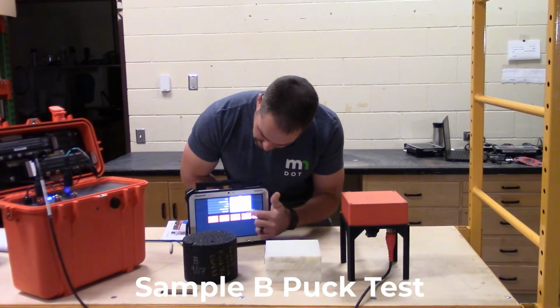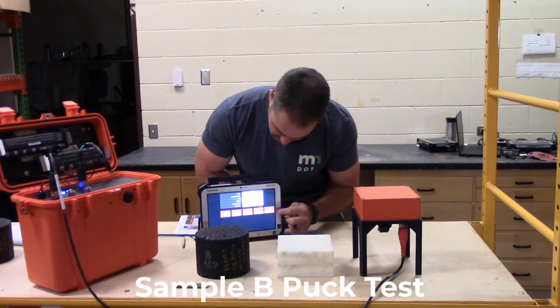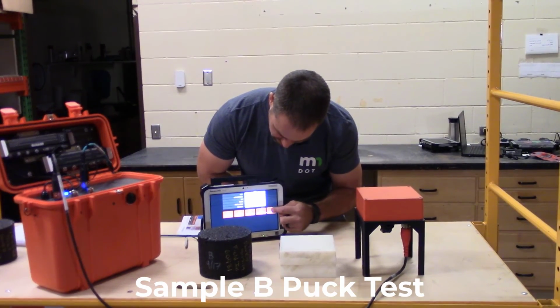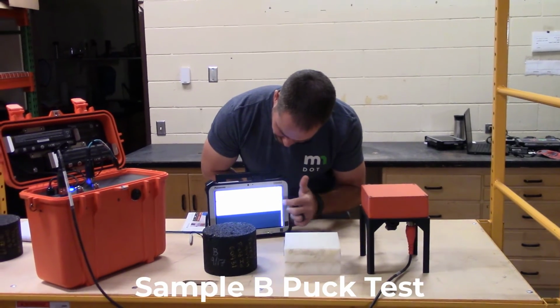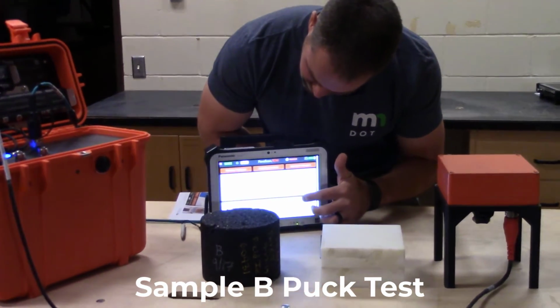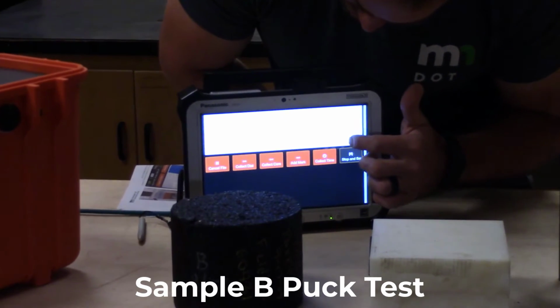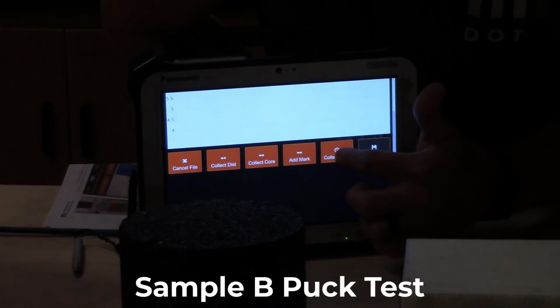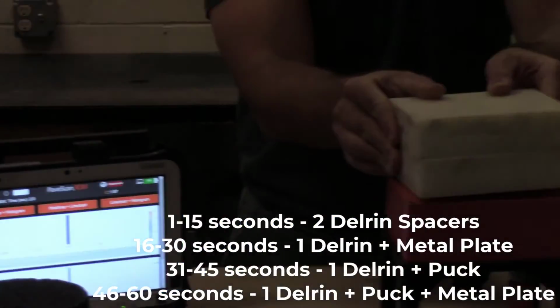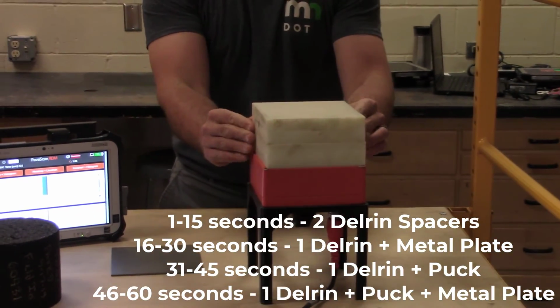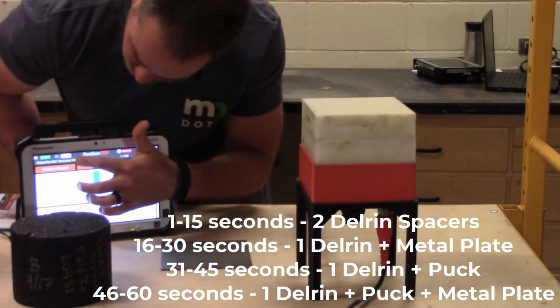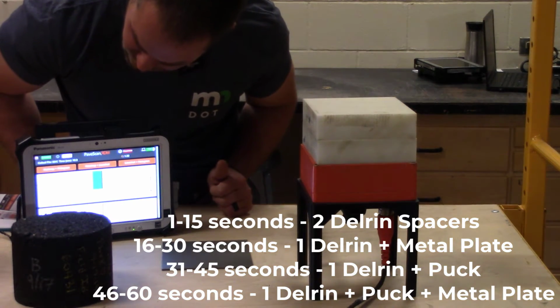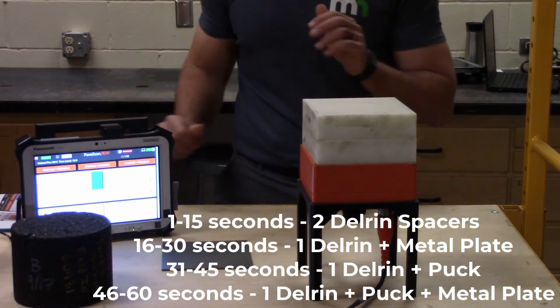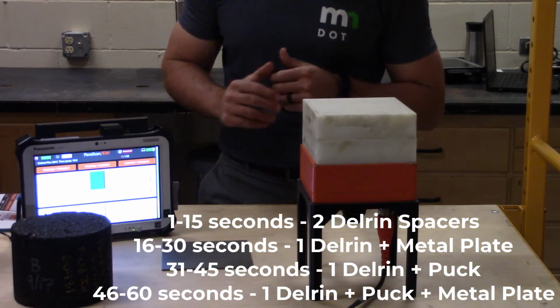Once we've finished entering the file root name with the -B at the end, we can go into collect data, scroll down, wait a little bit here, and we're going to go into collect time. And you want to make sure that you have your 2 Delrin spacers in place before this hits 10 seconds, because between 10 to 15 seconds, that's when it's doing the measurement of the Delrin spacers.